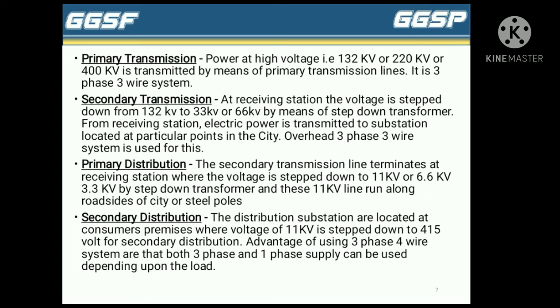The next part is primary distribution. The secondary transmission line terminates at a receiving station where the voltage is stepped down to 11 kV, or 6.6 kV, or 3.3 kV by a step-down transformer. The next part is secondary distribution — the distribution substations are located at the consumer's premises, where the voltage of 11 kV is stepped down to 415 volts, that is three-phase four-wire, for secondary distribution.